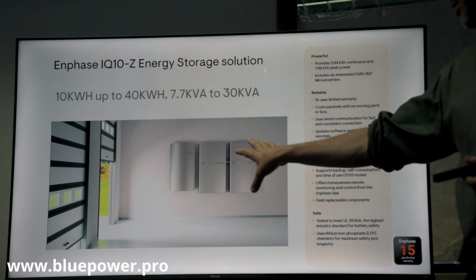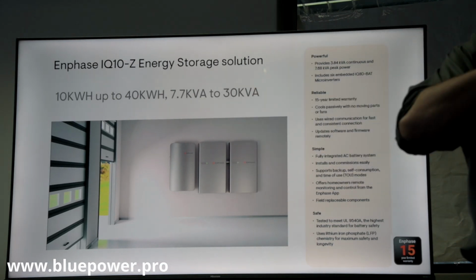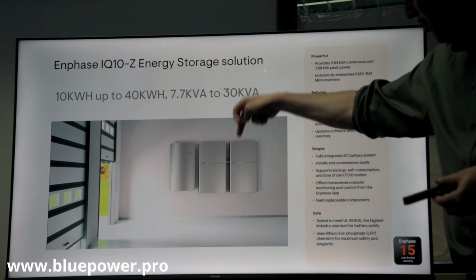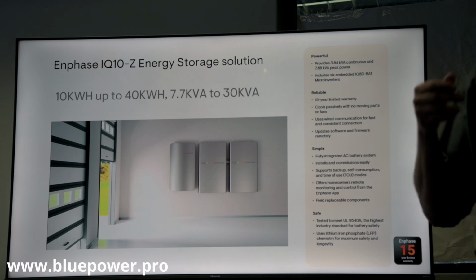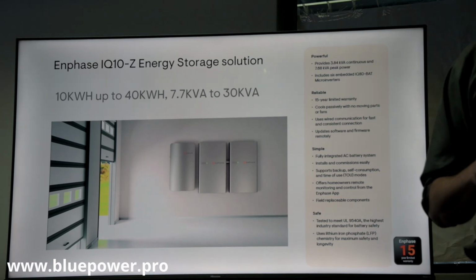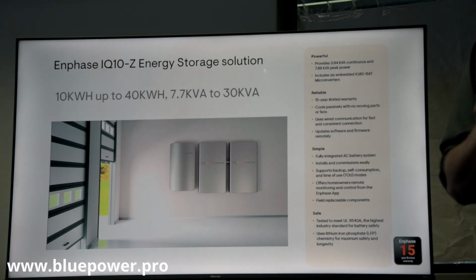Even if there's a fault on one of these batteries, you open it up. In fact, our field service technicians open it up and replace the microinverters built into the battery. So 70% of all faults can be fixed on site in a matter of hours, as opposed to going back to the distributor asking for an extra battery and waiting weeks for it to come back from wherever it is. Sorry to mention Victron again.